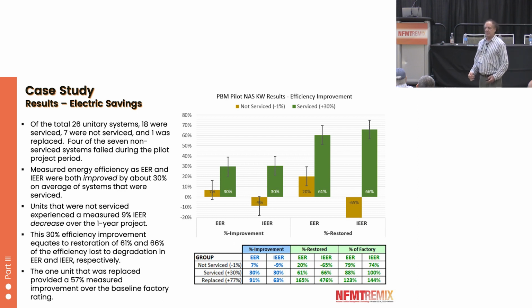that performance-based maintenance can do, is it can give you numbers to calculate, is it worth replacing this unit? So with this, we found that 1 unit was operating so poorly that the improvement of putting a new unit in would be economical, even though it wasn't dead yet. It's interesting that 4 of the 7 systems that were not given the extra service over the 1-year pilot had some sort of failure. Well, none of the 18 units that were serviced did.